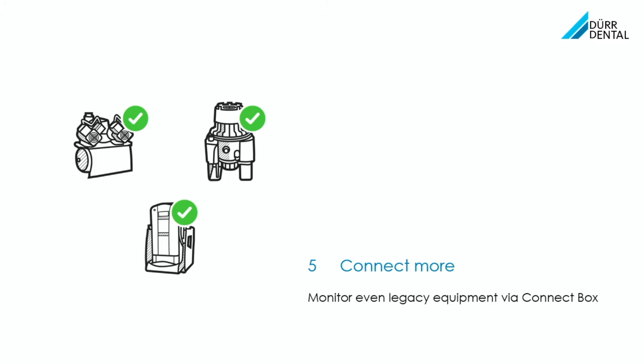We already have around 15,000 network-capable devices in the field today which can be assigned to VistaSoft Monitor from today on. But what about devices which don't have a network interface? For those, we have an additional hardware option called the ConnectBox. With the ConnectBox, you can connect non-network-capable equipment to VistaSoft Monitor as well, allowing you to cover your whole equipment room for monitoring.